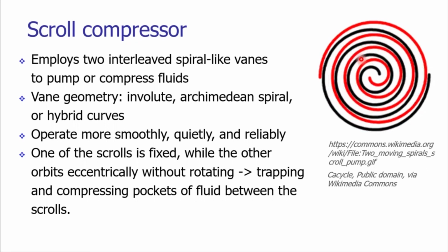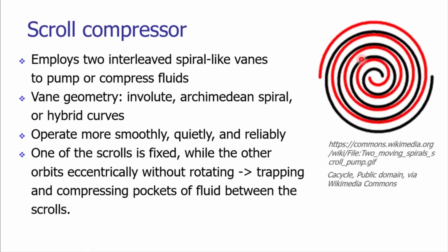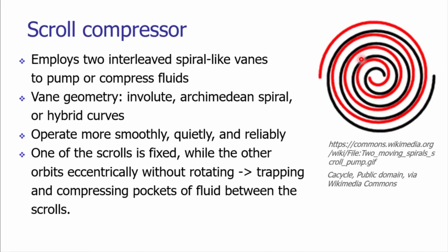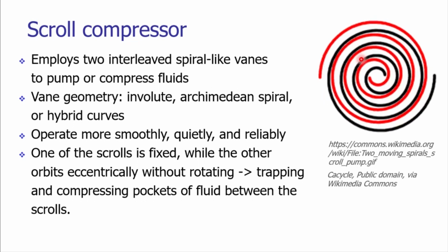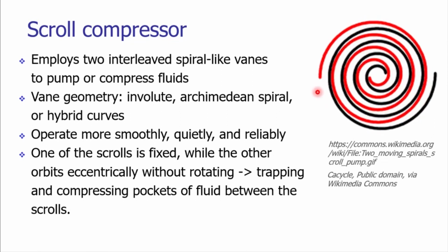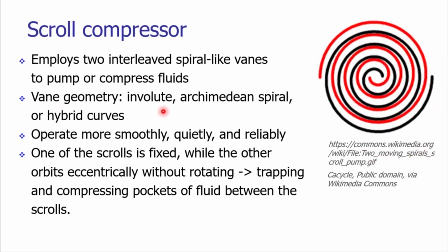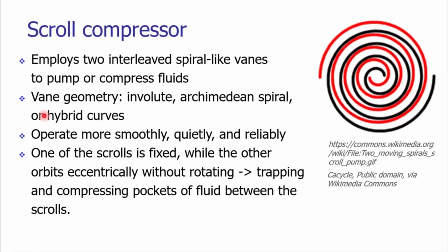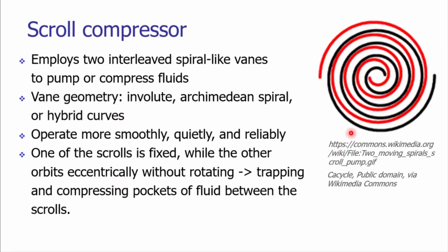When there is an increase in the volume, there is a decrease in pressure, the fluid will be sucked inside, and when the volume is getting reduced, the pressure will be increased. The same principle as the reciprocating compressor, or the general principle which we have seen in the previous pumps, has been employed over here, only the mechanism is different. The vane geometries are in general the involute type or Archimedean spiral type, or we can have hybrid curves as well.